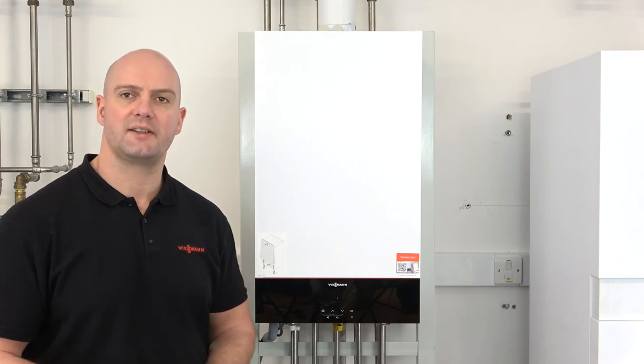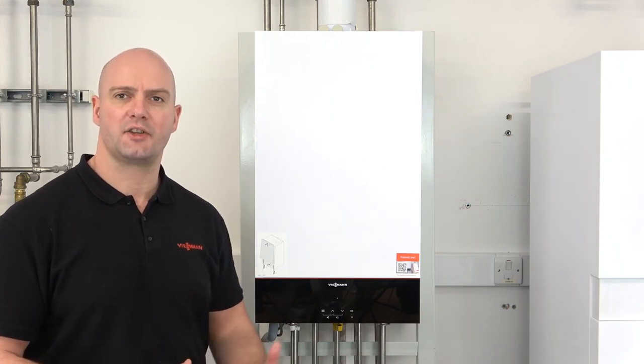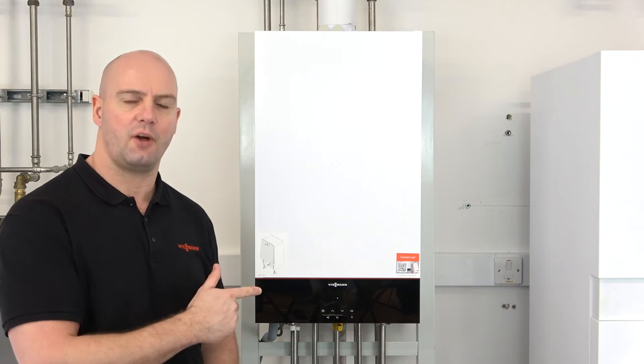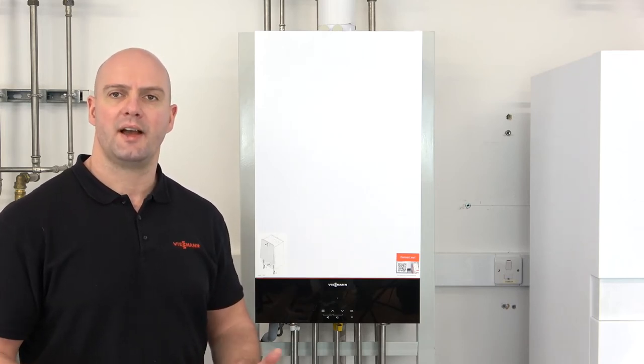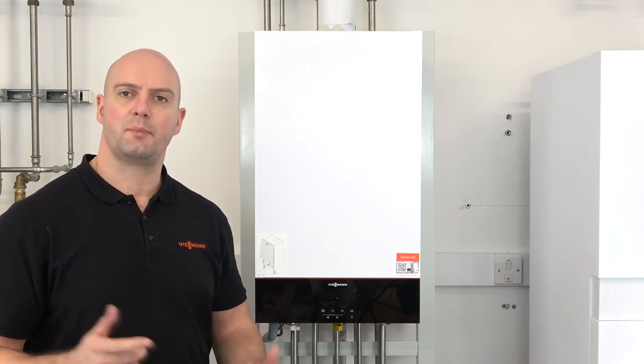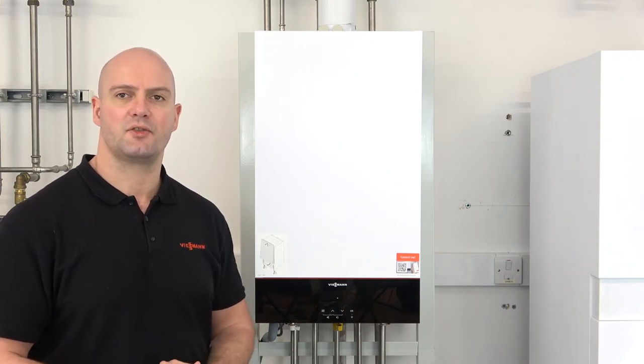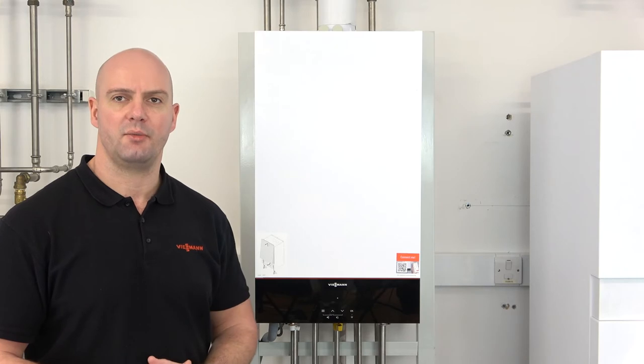Hi everyone, welcome along to our video today. Today we're going to show you how to access the service menu on our Viessmann 100 combi boiler. The service menu is what we sometimes refer to as the B menu. A full list of B codes can be found in our manufacturing instructions, which can be accessed on V-Books online.